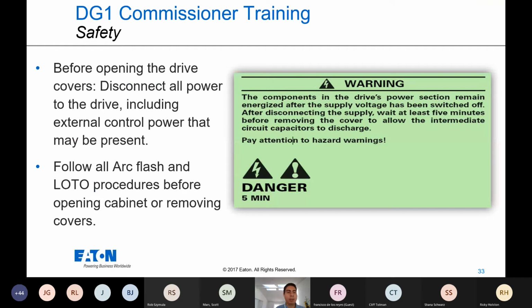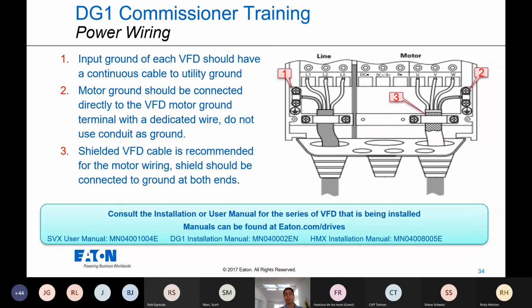Most importantly, before opening the drive, make sure that you follow lockout, tagout procedures and arc flash safety before opening the cover. Make sure that you have disconnected power from your panel board or MCC before touching any of the high voltage. One of the basics here is the grounding. Make sure that you have grounded your motor onto the drive. Follow the instructions from your manufacturer installation manual. Shielded VFD cable is recommended.